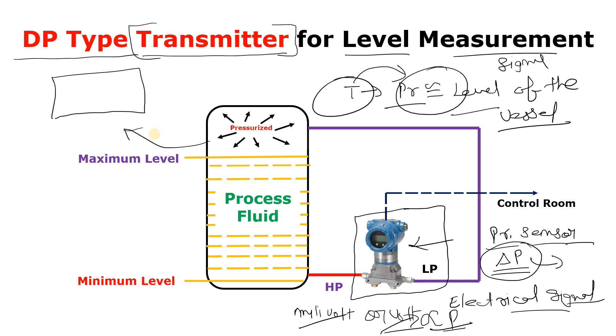When we look at the display in the control panel, we will find only the level. It goes through controllers and there will be a marshalling room in your control room, but that is a different thing. Simply, you can understand like that how this transmitter works. Got my point? Now this is a very simple arrangement which I have shown here. The arrangement can be of different types. In this arrangement the DP transmitter is here, but it depends on your installation and your arrangement, and on the basis of that the calibration is done.